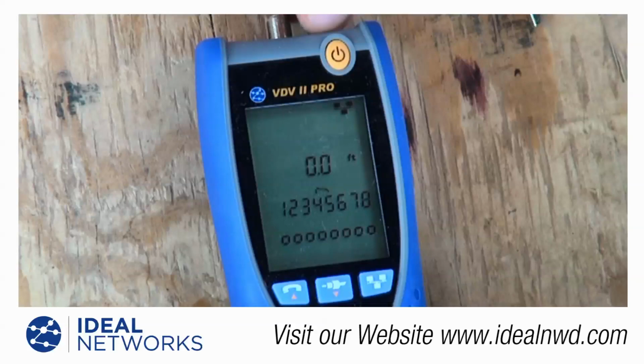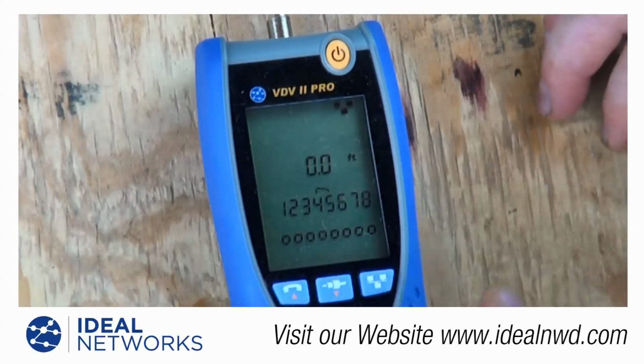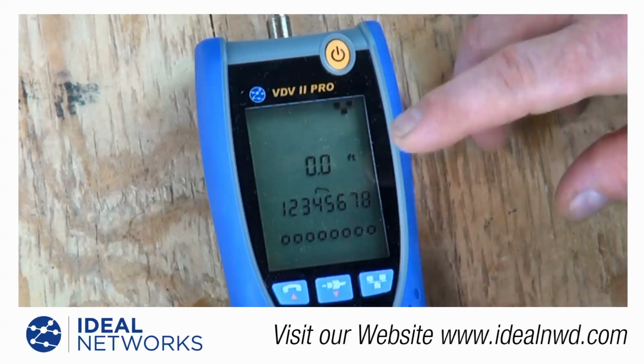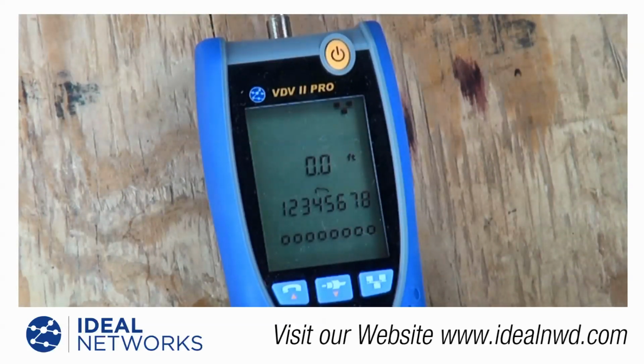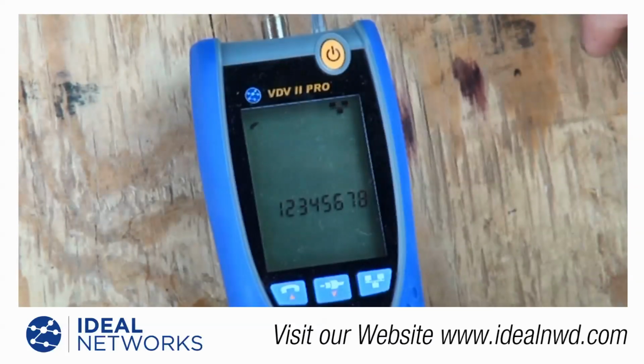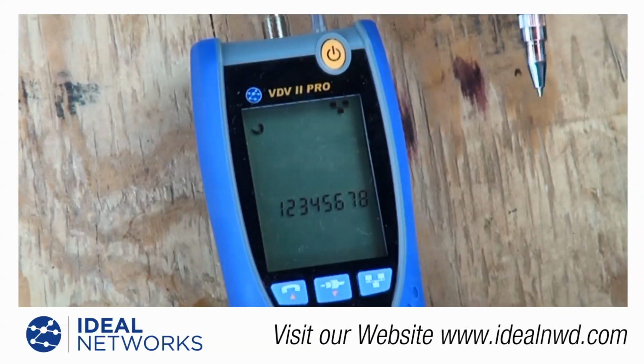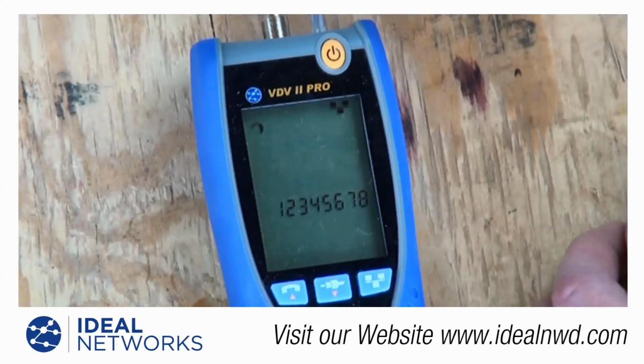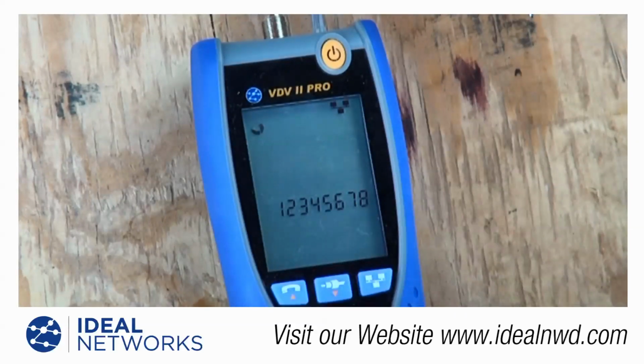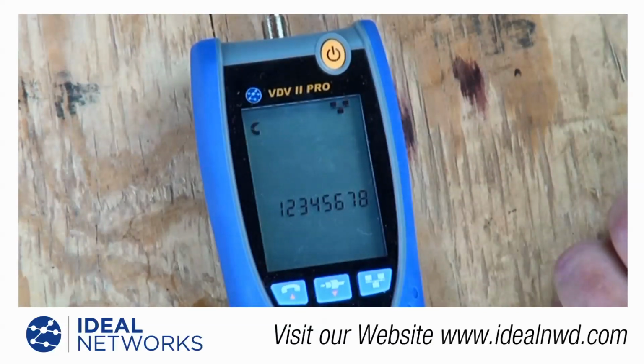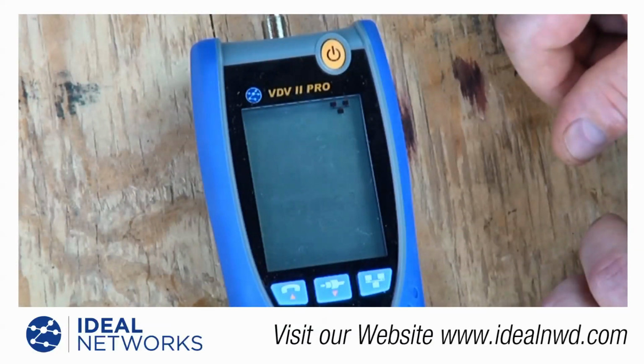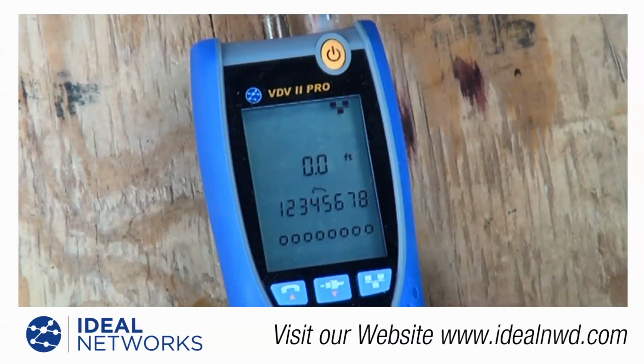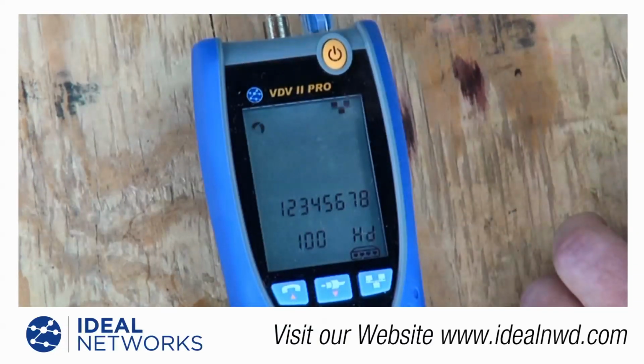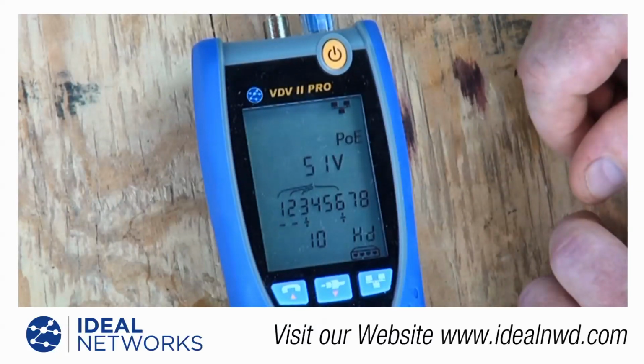Now some interesting things about the VDV, and what people will do - say I'm in the data section and I plugged a phone line into the data jack. Well, the tester goes into what we refer to as a safe mode, saying, I see a voltage, I kind of recognize it, but you're not on the right port. The tester's frozen now and won't let me do other things. If I unplug that, it comes out of safe mode, and if I plug the Ethernet switch back into the tester, it'll indicate it sees the switch and the PoE voltages again.